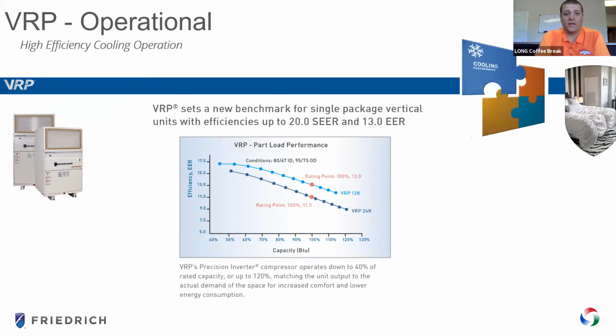So with the VRP, you're able to see here their efficiencies and the ability for it to increase in efficiency as you're going down in capacity. And that's really the whole name of the game when it comes to improving efficiencies: matching your part load. Majority of the time, as you all know, we're not running at full capacity. It's not a design day. In Colorado here, it's probably 70 to 80 degrees. We might get an afternoon thunderstorm, but it's not going to be too humid.